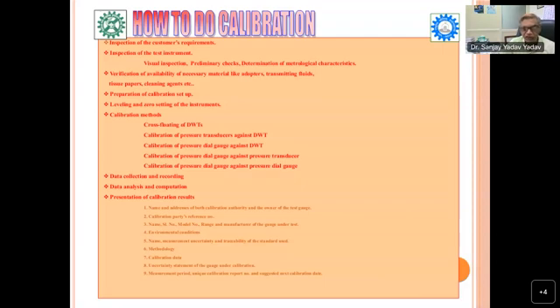Third one is calibration of pressure dial gauge against pressure transducer, and the fourth one is calibration of dial gauge against dial gauge. Please remember, you cannot calibrate equipment of a better quality with lower accuracy equipment. It means you cannot calibrate a high accuracy pressure transducer against the dial gauge.